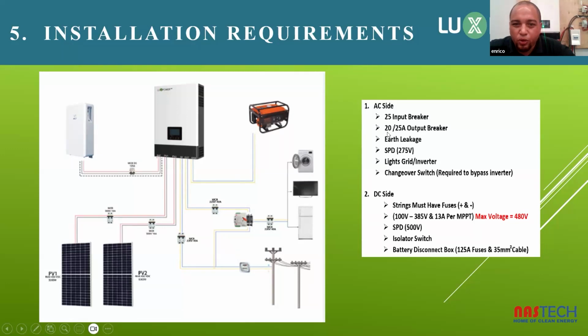So the output of the unit will be 20 amps times the 230. With a 20 amp breaker, you will get up to 4.6 kilowatts of power from the unit. But because of standards, you don't usually find a 22 amp breaker. Therefore, we give you the two recommendations of a 20 and a 25 amp.